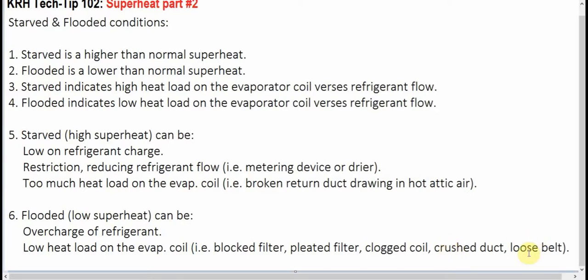Or in a light commercial application, it could be a loose belt. It's very common to see loose belts on the blower, and that will cause a flooded condition. Now going back to the overcharge, believe it or not, it is pretty common to find systems that have been overcharged. That's typically because the technician who overcharged it was not following the starved and flooded condition guidelines regarding superheat. They were merely adding Freon based on the boiling point of the evaporator, and usually they're not even checking superheat. They're just adding refrigerant to get that saturation temperature or boiling point above 32 or 35 degrees, and that will lead to an overcharge condition.